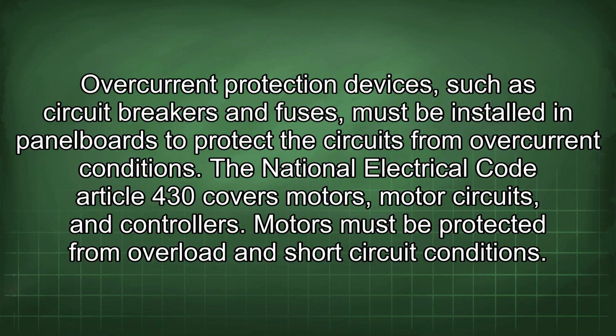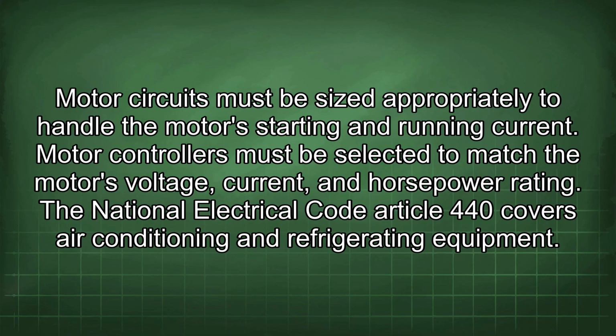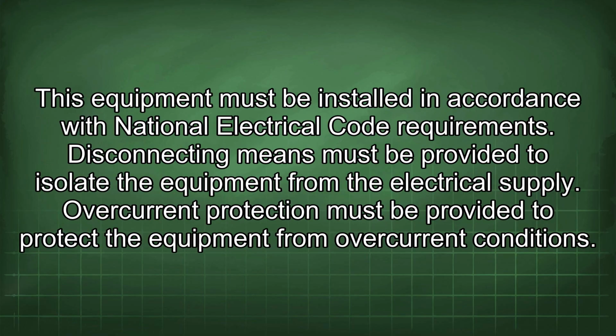overcurrent conditions. The National Electrical Code Article 430 covers motors, motor circuits, and controllers. Motors must be protected from overload and short-circuit conditions. Motor circuits must be sized appropriately to handle the motor's starting and running current. Motor controllers must be selected to match the motor's voltage, current, and horsepower rating. The National Electrical Code Article 440 covers air conditioning and refrigerating equipment. This equipment must be installed in accordance with National Electrical Code requirements. Disconnecting means must be provided to isolate the equipment from the electrical supply. Overcurrent protection must be provided to protect the equipment from overcurrent conditions.